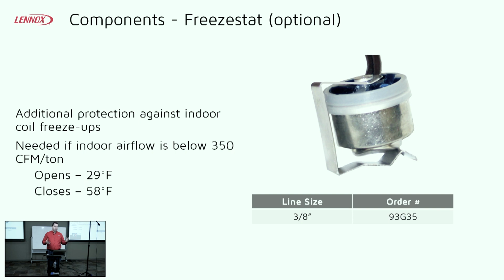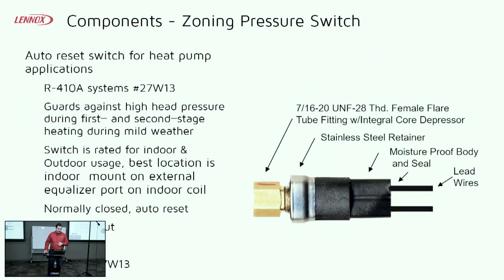So I want to have like 600 CFM at a minimum, and some folks are wanting to do 300-400 CFM per zone. You know, you're flirting with disaster there. So Freezestat can be a good means of protection. Maybe not that low of a situation, but if you have a zone that maybe runs a little bit long, if you're having an occasional nuisance freeze up, that can be a good step to take. Now this zoning pressure switch, this is a requirement.